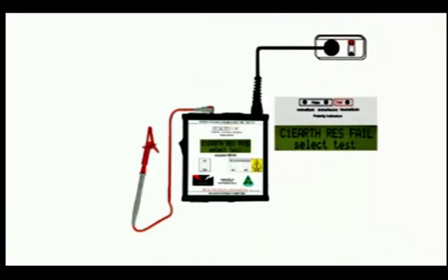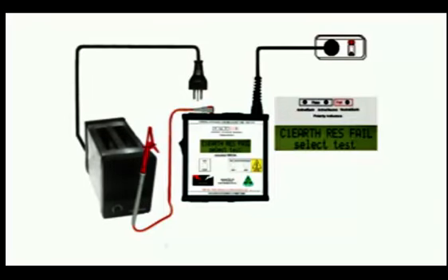We're going to test an earthed appliance. That's Class 1. So we'll need a test probe to check the earth. In fact, the procedure is the same for Class 1 and Class 2. The difference lies in the interpretation of the results. The Class 1 appliance in this case is a toaster, and it's safer to assume that the appliance may have a fault until we've tested it to prove otherwise.